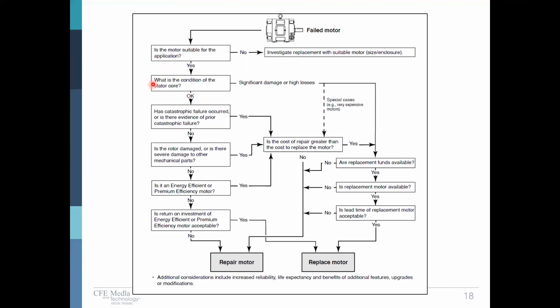Condition of the stator core. It's gone into the service center and is being evaluated. If we find damage that's showing high losses, then we say, wait a minute, is it going to be economical? We move down. Okay, we want to replace it. Well, are replacement funds available? Is there money in the budget? If there is, we go down.